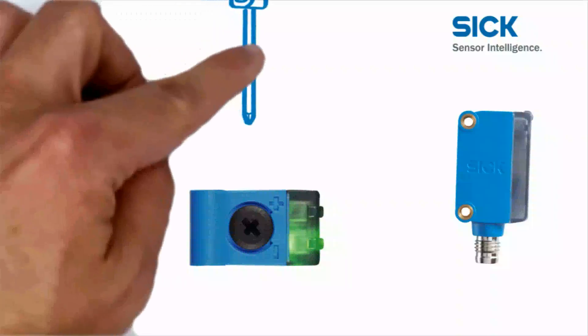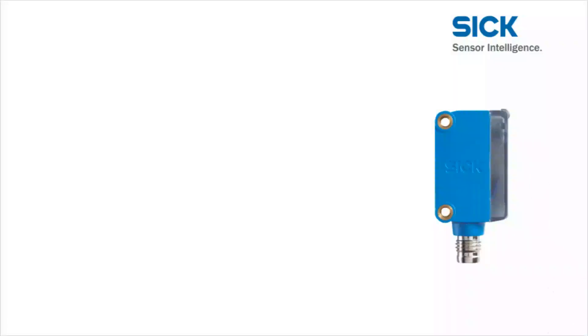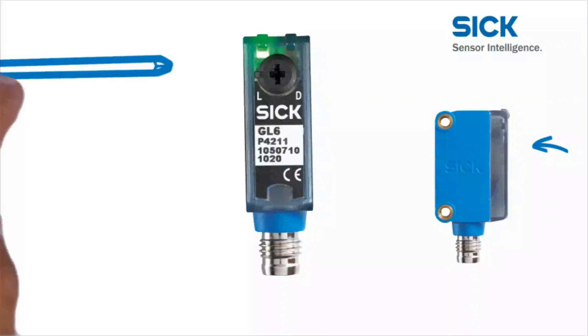All adjustments can be made quickly and easily using a simple cross-head screwdriver. The sensitivity and scanning distance of the GL6 are adjusted using the large rotary potentiometer on the top. The set screw on the rear can be used to set the sensor to light or dark switching.